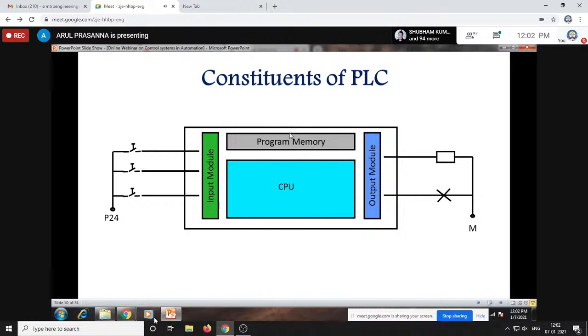Apart from the on-chip memory and CPU, the PLC has specific modules called the input module and output module. This is what PLC has in addition compared to our normal controllers, which just have direct terminals connected to the CPU directly. But here there's no direct connection of input and output with the CPU.